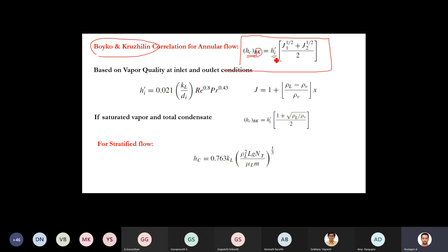This BK represents Boyko and Kruzhilin. This h_i' is the heat transfer coefficient, normally measured based on inlet and outlet conditions. So this is single phase. Then this h_i' is corrected by the J value, (J1^0.5 + J2^0.5)/2, where J is represented by 1 + (ρL/ρV − 1)X, where X is the vapor quality. Even if you refer to steam tables, you can get this value, steam quality or vapor quality, which means mass of vapor per total mass. If vapor quality is 1, it is completely vapor, no liquid. You can define vapor quality as MV divided by (MV plus ML), mass of vapor divided by total mass. If ML comes down, this becomes 1. If ML increases, MV comes down, your vapor quality comes down, which means it is mostly liquid.